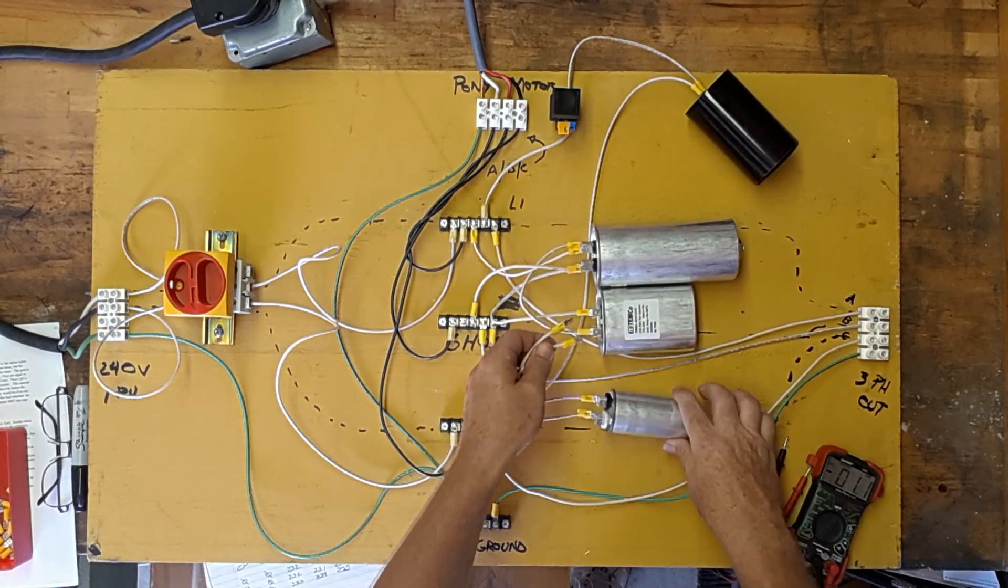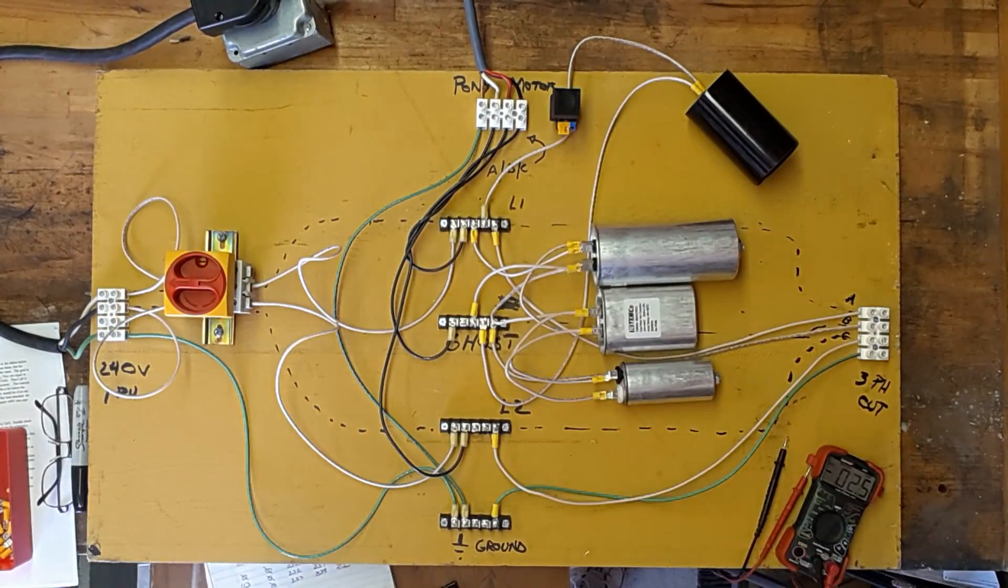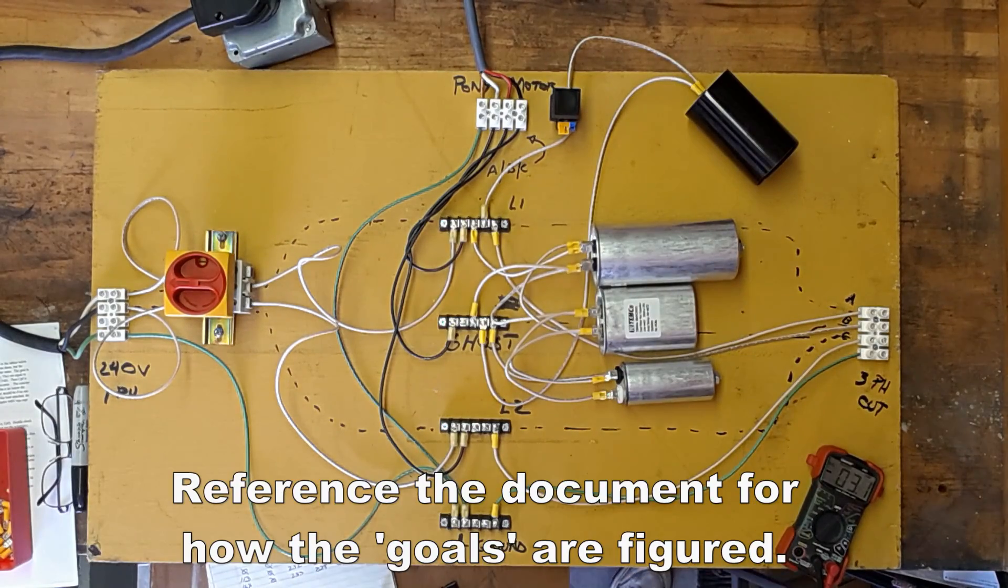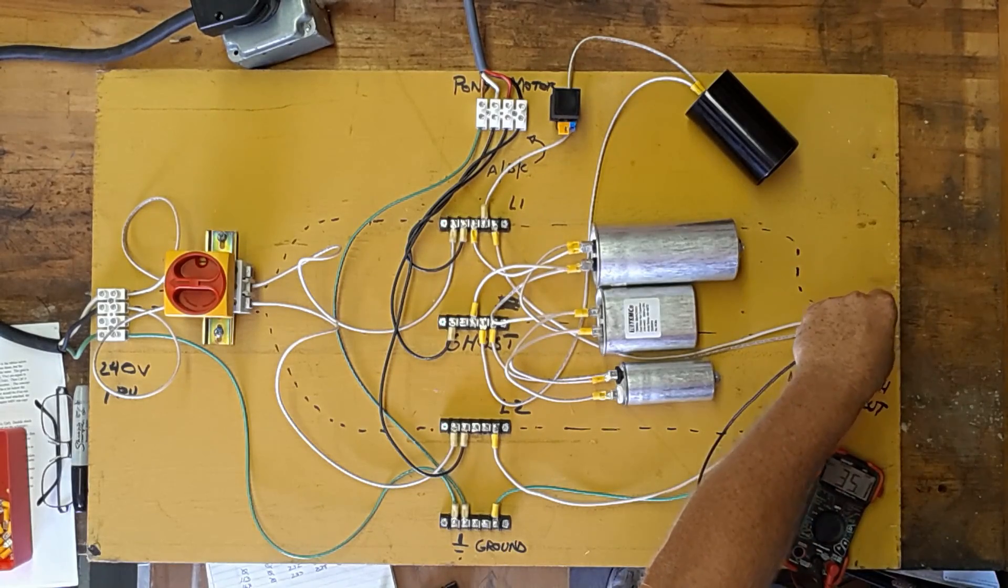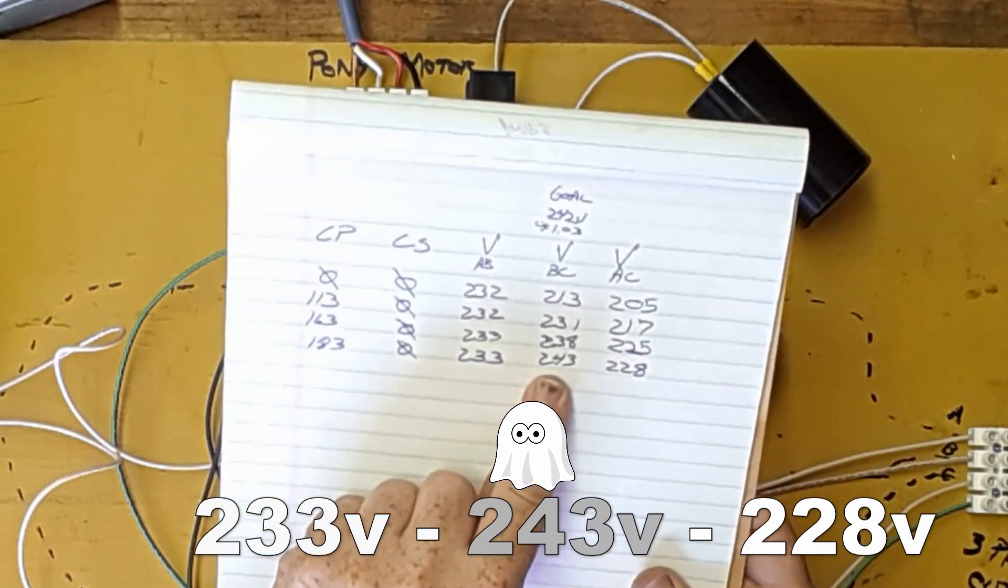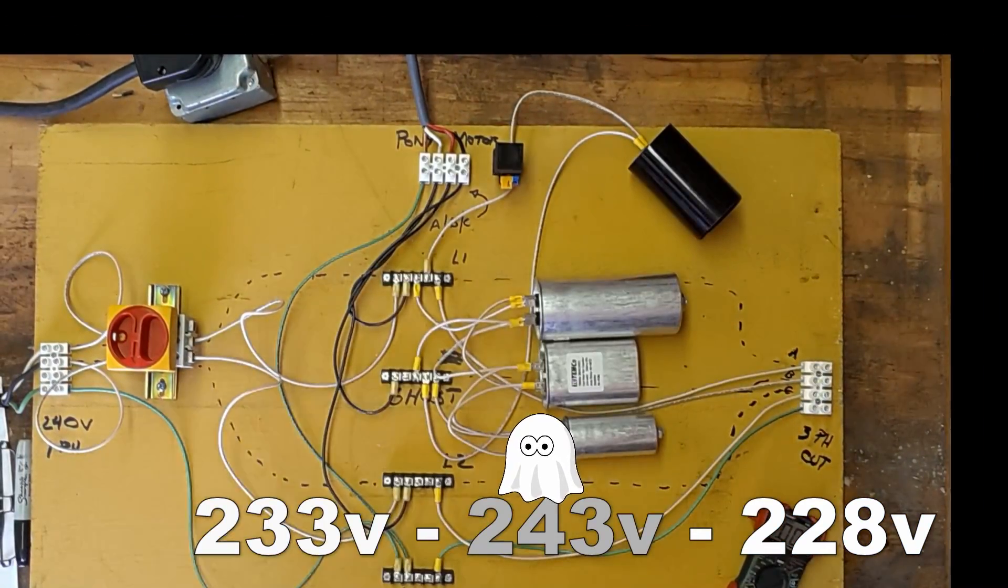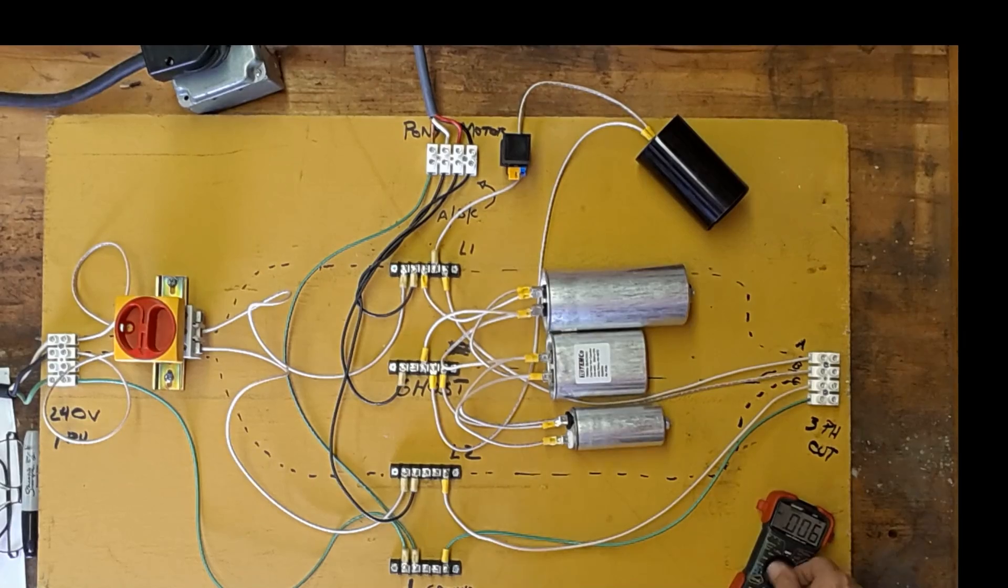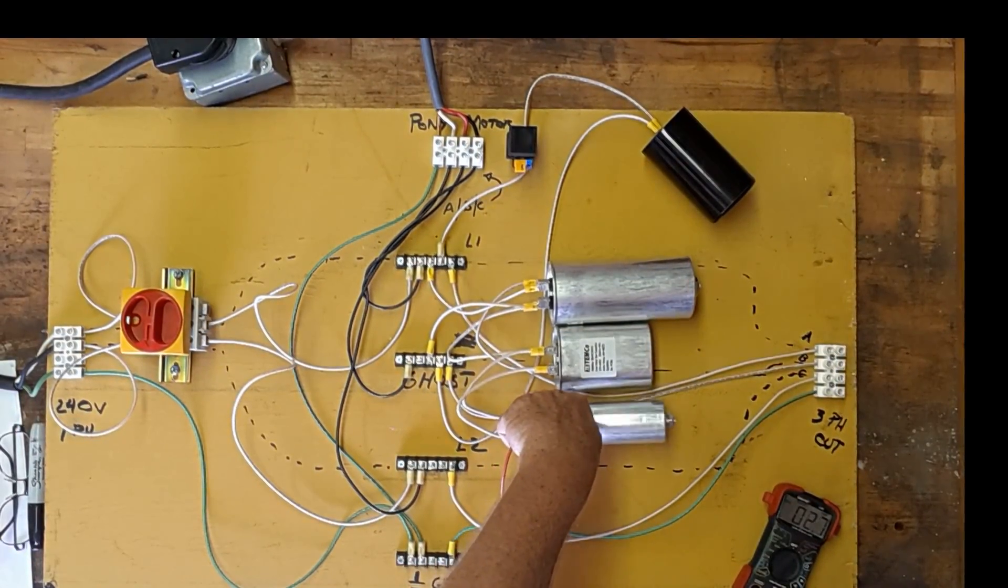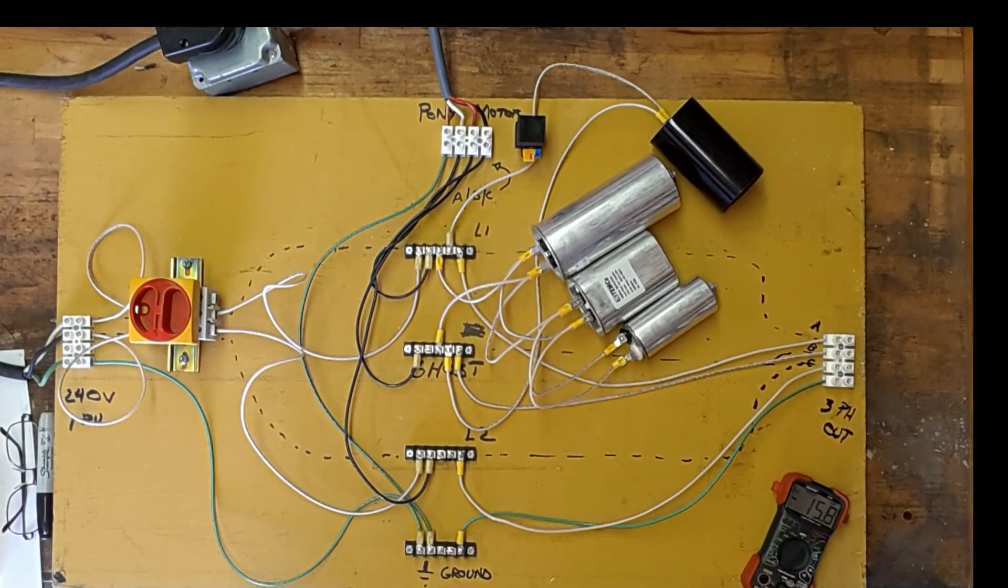This is a 20 microfarad. We're going to add it. And start it again. Okay. We reached our goal. 242. We're at 243. Perfect. So this one's good. Double check the voltage. Make sure the caps have drained one more time. We're good. So that does the one leg. That's done. Now we have to do the same thing from here to here.